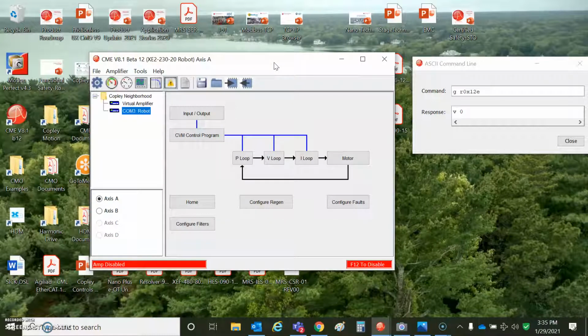If you just get bogus data without a CRC fault and no warning, well, that's bad. It's like, I'm going along and all of a sudden I went to plus 30 million, minus 30 million, and then back to zero without a warning. There's a streaming bit error, which should say, hey drive, I'm going to set this bit, I'm going to give you some data, I don't trust it, it's ridiculous, so don't use it. And then the next sample, I'll give you some good data. So there are many layers of protection here to keep things going, even with these serial encoders bundled with 16 feet of cross-coupling motor power wires in the same package with your feedback cable.